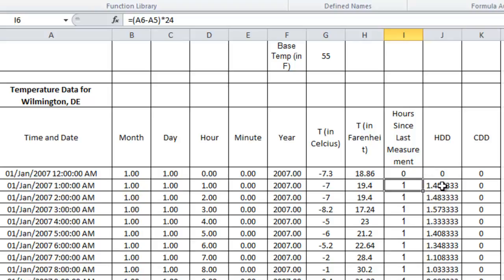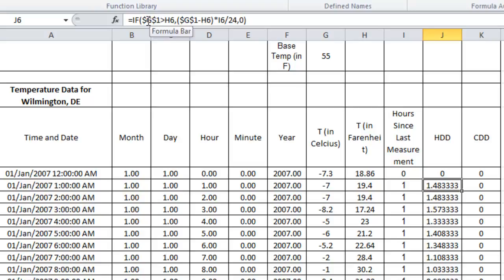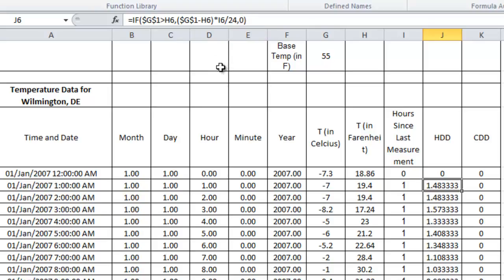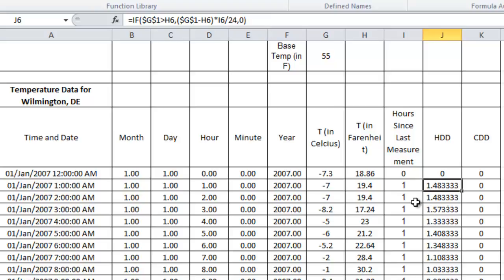To calculate heating degree days, you need to know your base temperature. If the outside temperature is less than the base temperature, you should have heating degree days; otherwise, heating degree days should be zero. The IF statement handles this: if the base temperature is greater than the outside temperature, calculate the formula; if not, set heating degree days to zero. The formula is: (base temperature − outside temperature in Fahrenheit) × (hours since last measurement) ÷ 24.